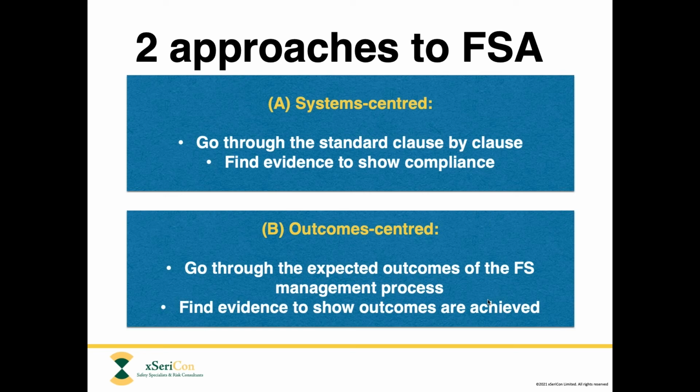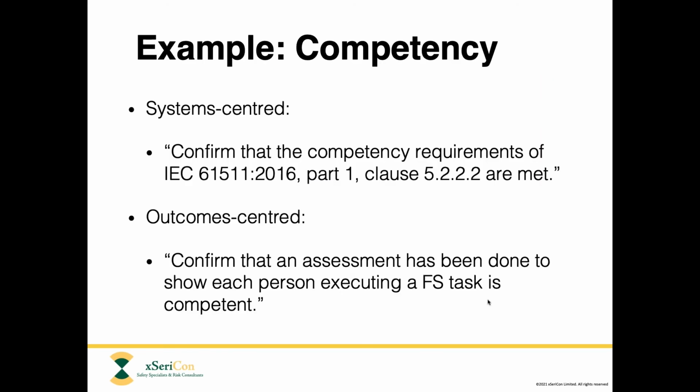Let me give you an example. Supposing we are considering the requirement that anyone who performs a task relating to the safety instrumented system must be competent for that task. So the system-centered approach would say, I see this requirement in the standard part 1, clause 5.2.2.2, and it lists out some specific competency requirements there. So I, as your FSA consultant, would say, okay, please show me evidence of compliance with this clause.